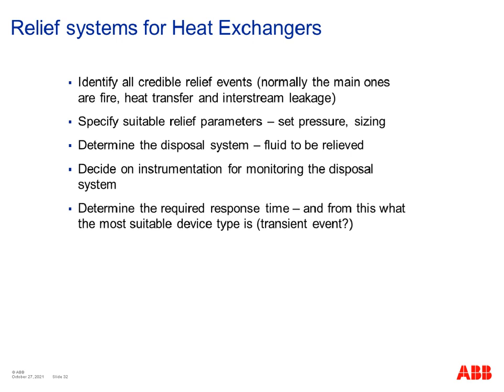You would decide on the instrumentation for monitoring the disposal system, so you can work out what's actually happened in a relief event, and the operators can work that out in real time. You would determine the required response time, and from this, what the most suitable relief device type is. So again, we're thinking about the transient event in the tube failure case really here, and whether you want to go for a rupture disc because it's going to react more quickly in that event than a relief valve, sorry.